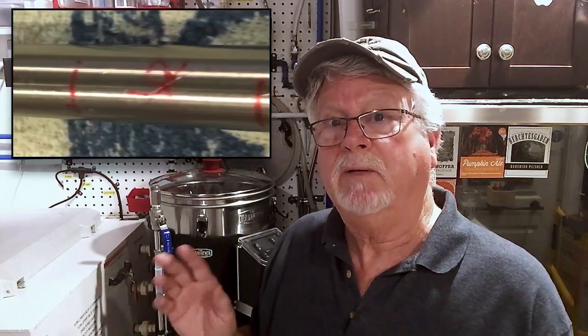Using the etched markings visible on the outside of the boiler, I marked off a section of the discharge pipe between 5.5 and 7 gallons, and using a pipe cutting tool, I removed a section of the discharge pipe, including a 1/2 inch on both sides for the hose clamps. I deburred the edges, installed a piece of high-temp silicone tubing, and secured it with a couple of hose clamps.